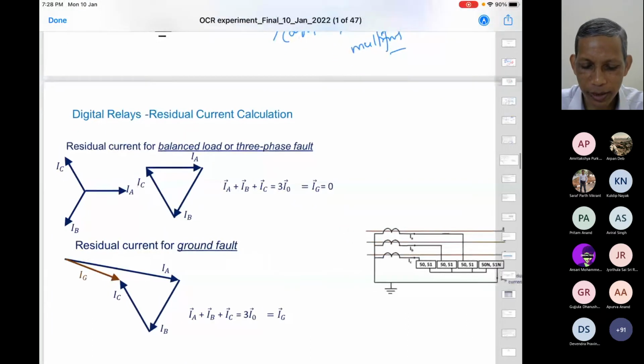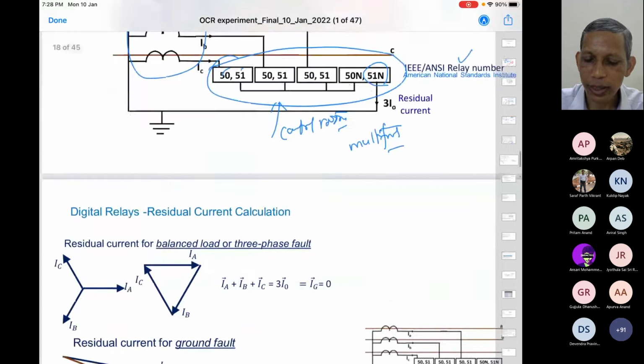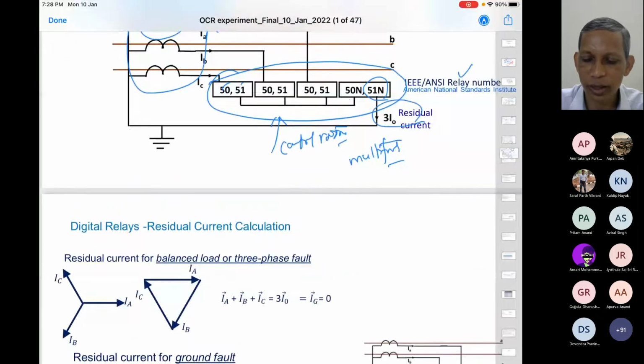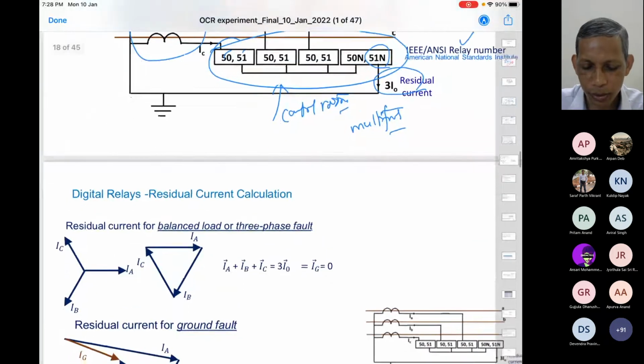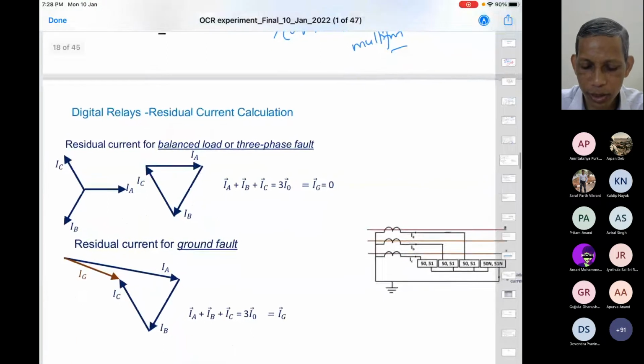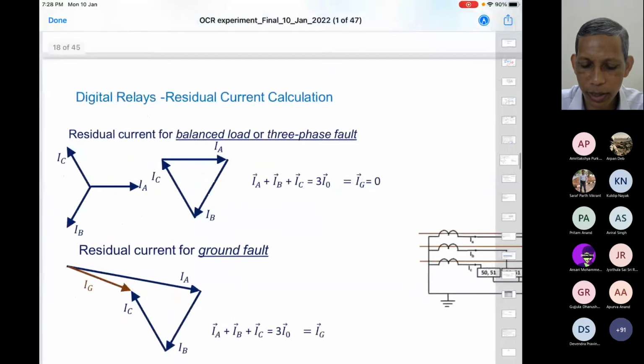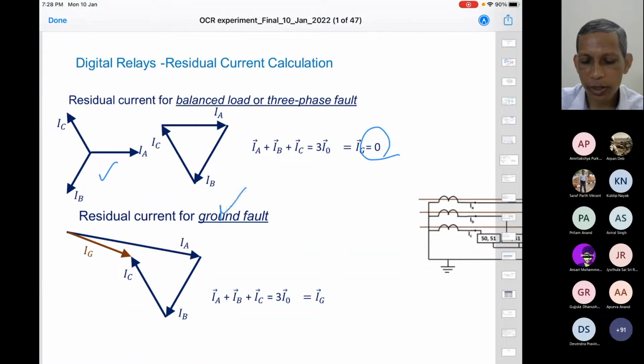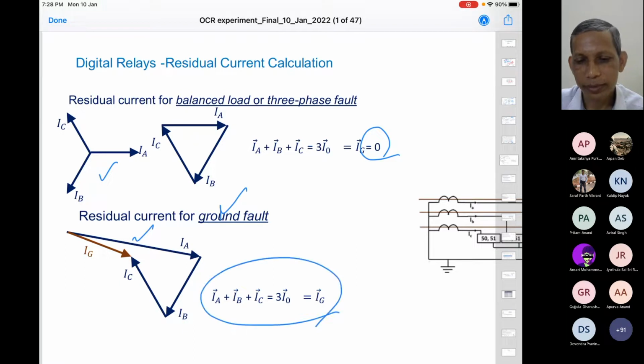In these numerical relays, one thing: what is the ground current we are talking about? Residual current, ground current. You'll study the phasor analysis and fault analysis later on. Take IA, IB, IC. If you add all of these, normally this current is 0. IA plus IB plus IC is 0, that you know. But whenever a ground fault is involved, let us say on phase A, the phase A current becomes substantially high, and B and C are like that. So if you add them at that time, the sum is no longer zero.